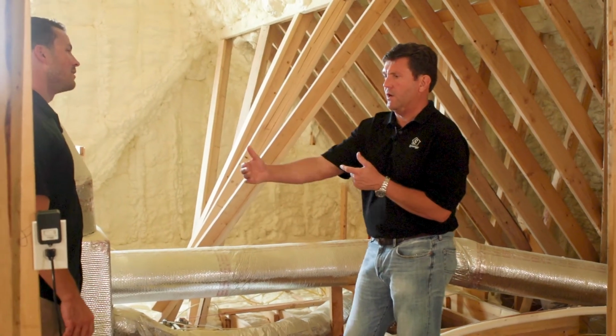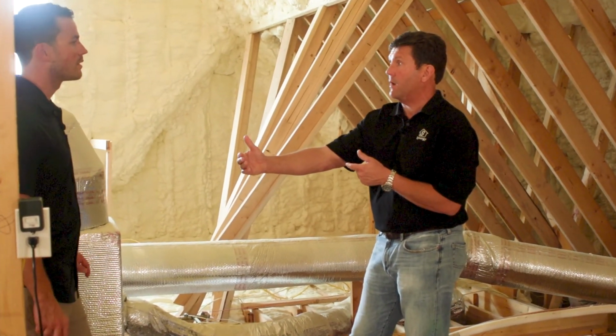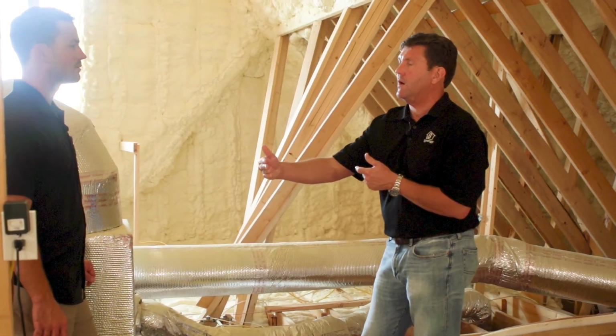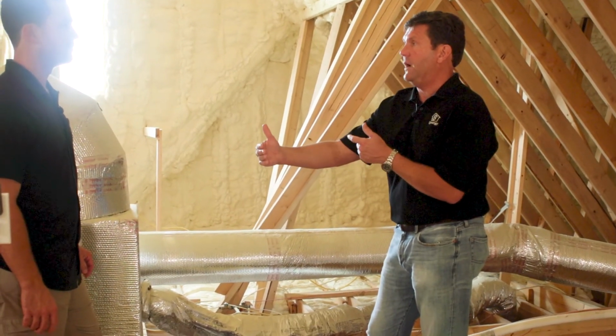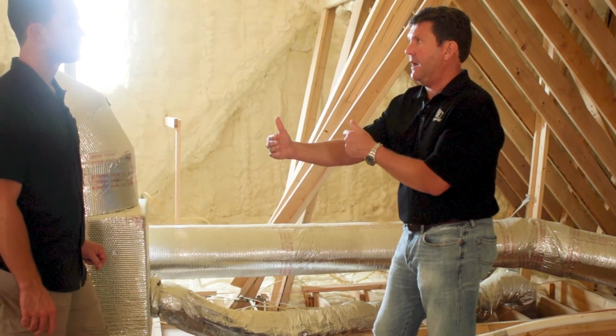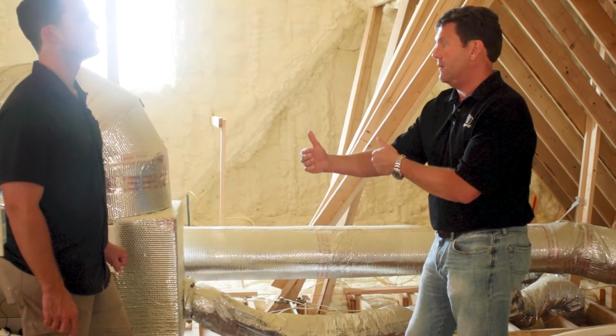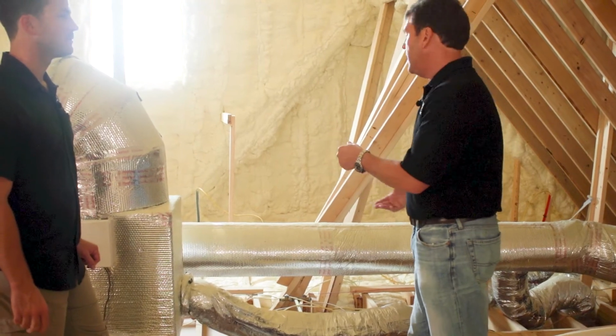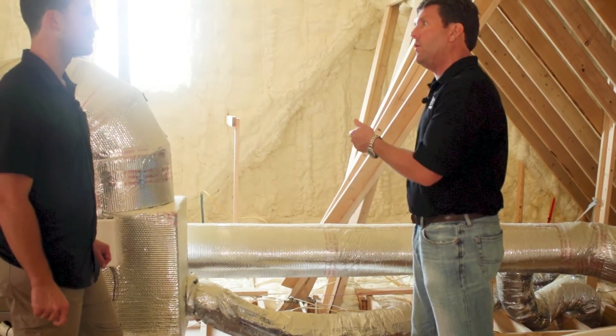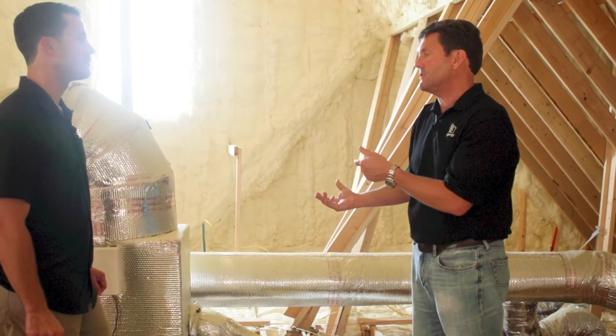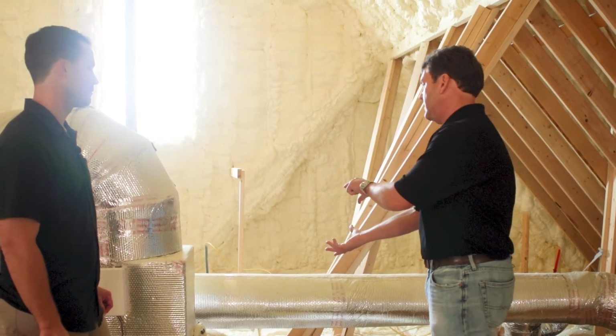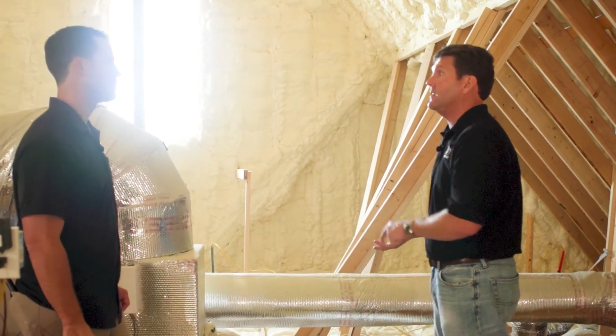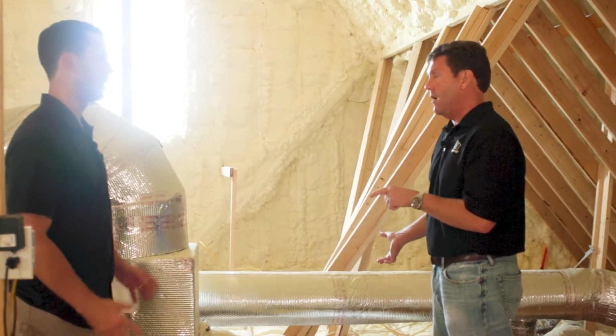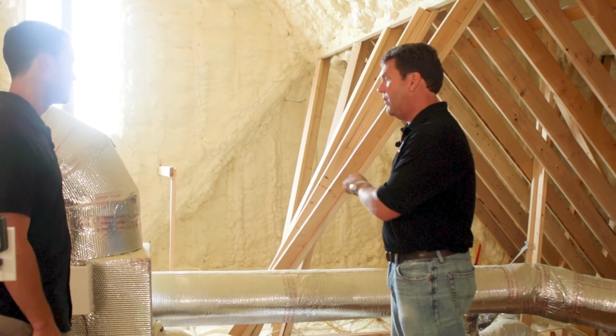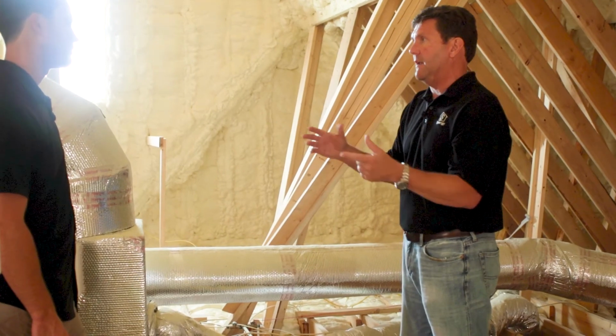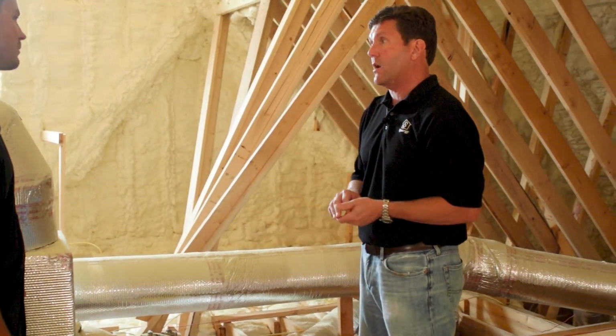It's big. We looked downstairs in that master bedroom earlier at that jumper duct. If we closed that bedroom door and didn't have a jumper duct, that air couldn't get pulled back to the unit. The return doesn't know it, so all day long it would pull outside air into the house. So when you start messing with fresh air and ventilation, there's a lot of people who don't want to deal with it because the system is complicated. If you don't get these jumper ducts balanced correctly, you're going to have problems.